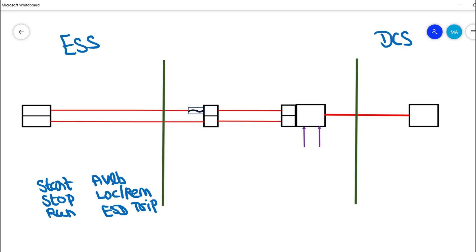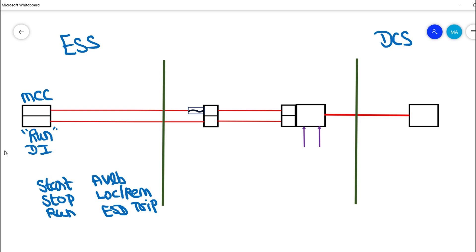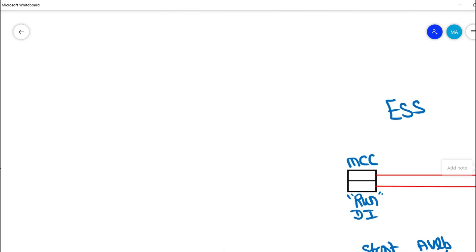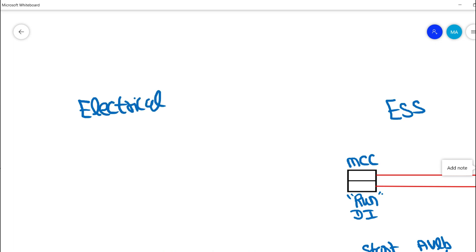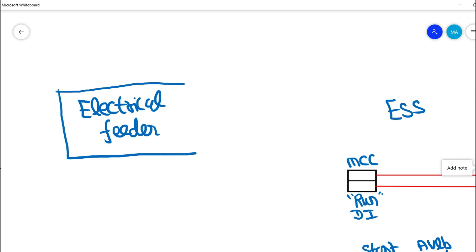These are the basic control signals looped between the electrical substation motor control center and DCS. In this video we take the example of run feedback, which is considered a digital input from the motor control center. Let me briefly explain what a motor control center is. An electrical feeder contains both electrical and instrument control supply signals and relay units needed to run a motor.